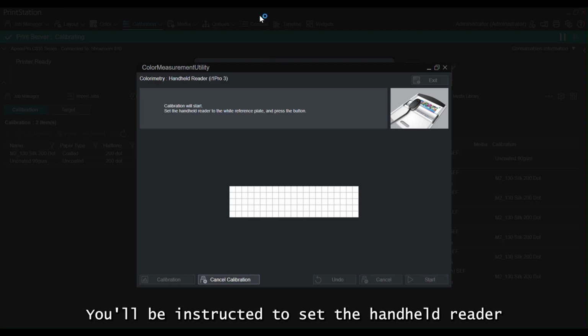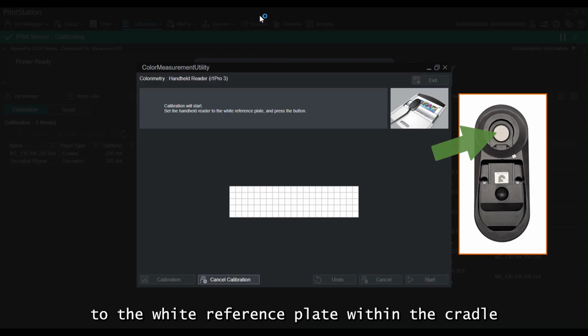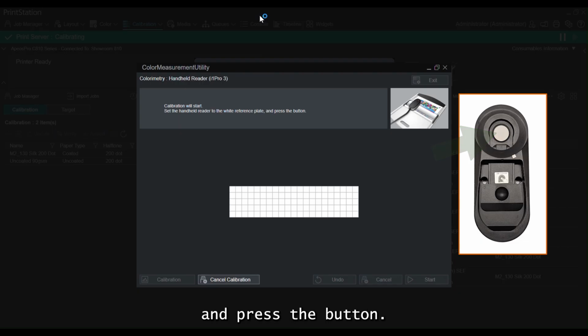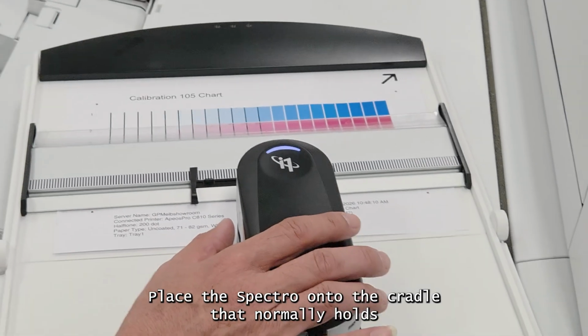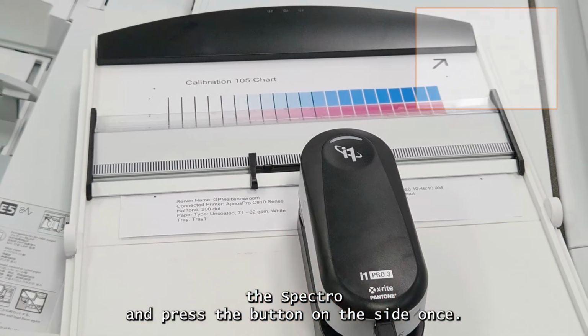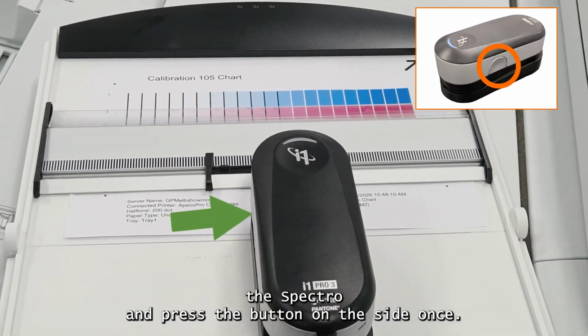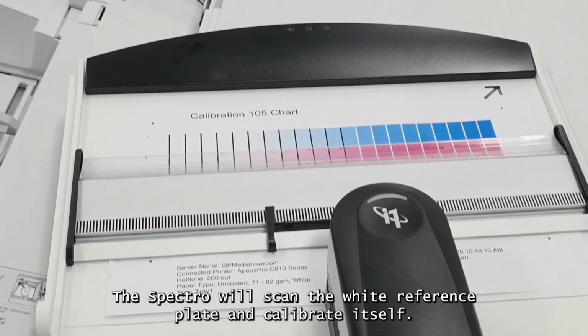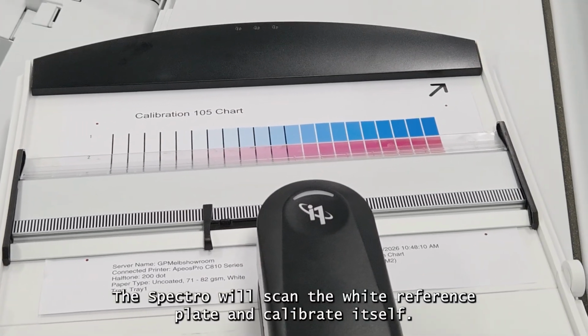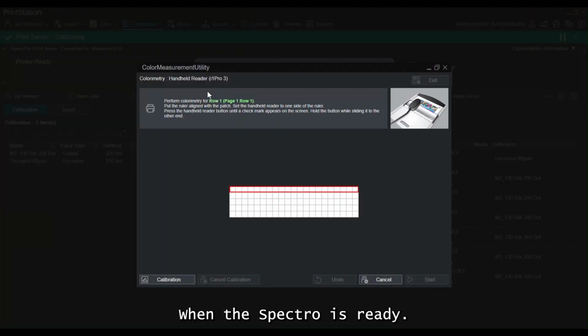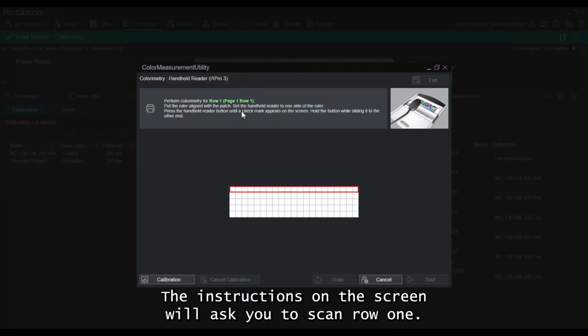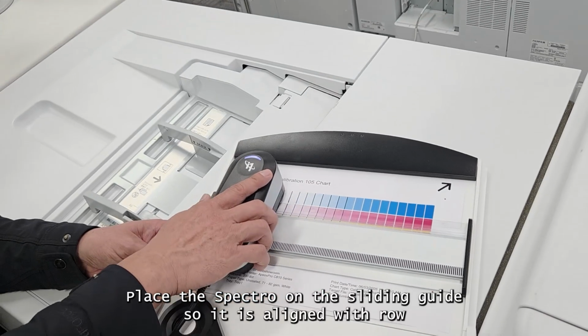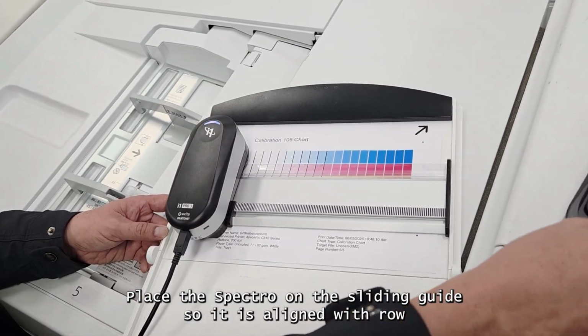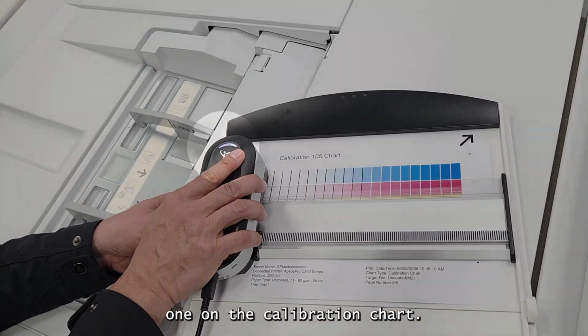You'll be instructed to set the handheld reader to the white reference plate within the cradle, and press the button. Place the spectro onto the cradle that normally holds the spectro, and press the button on the side once. The spectro will scan the white reference plate and calibrate itself. When the spectro is ready, the instructions on the screen will ask you to scan row 1. Place the spectro on the sliding guide so it is aligned with row 1 on the calibration chart.